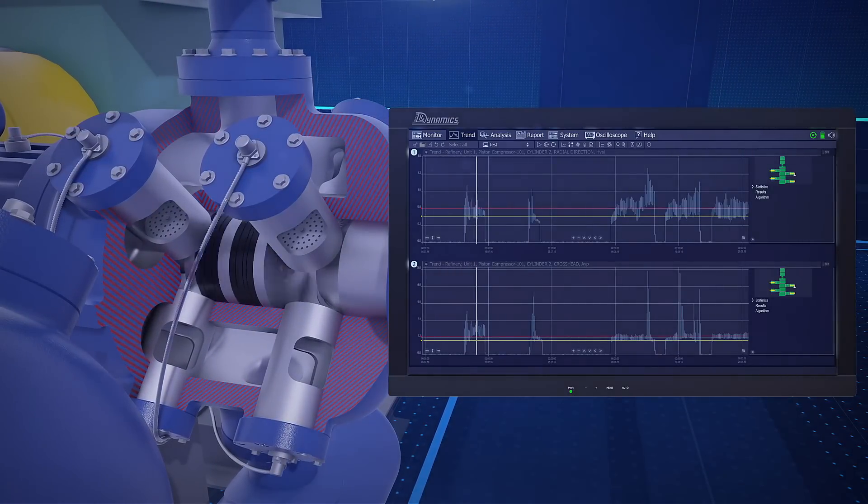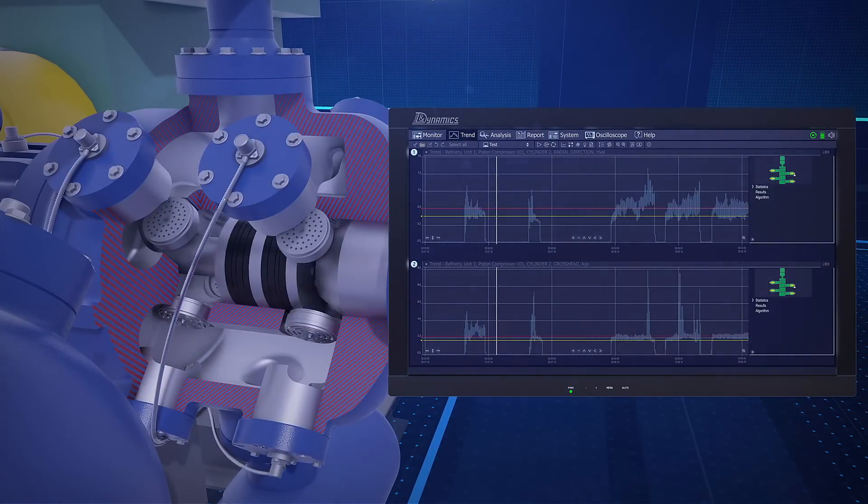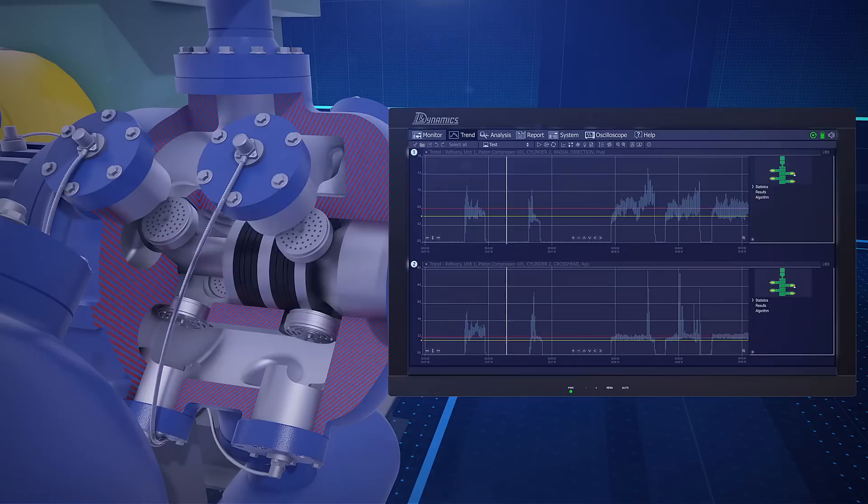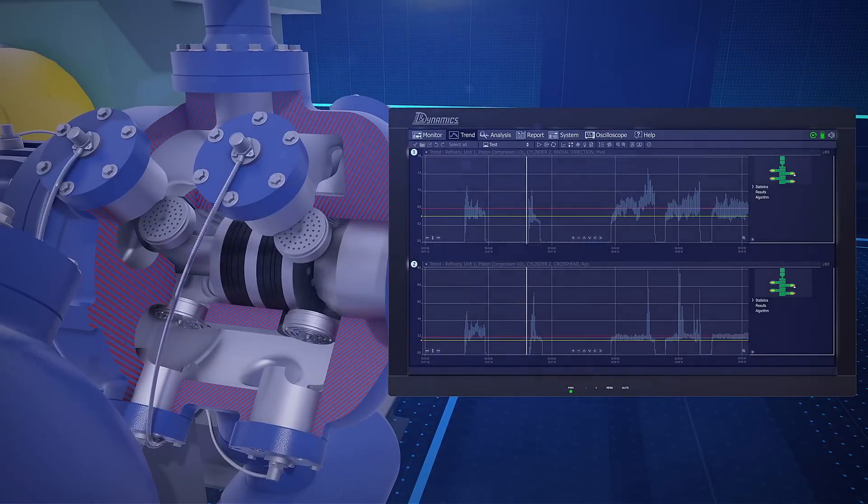The upper trend shows deterioration of the valves. As you can see, on average, every week the compressor faced valve issues.